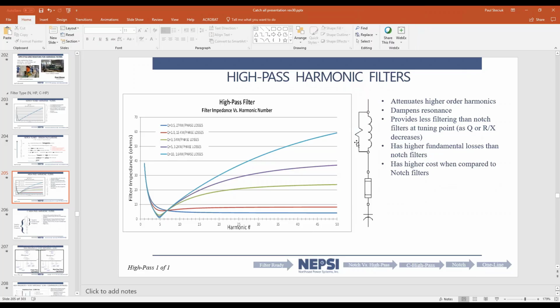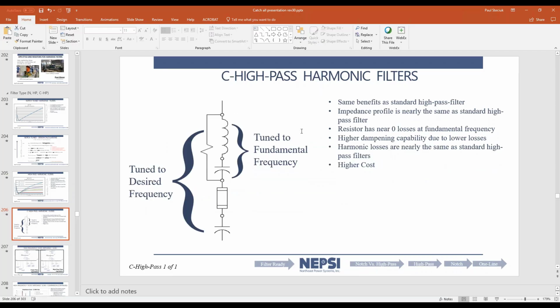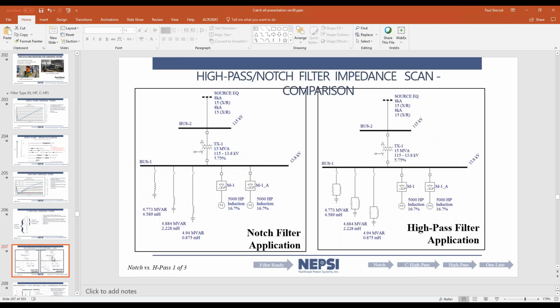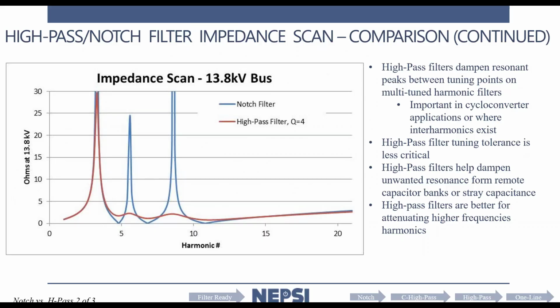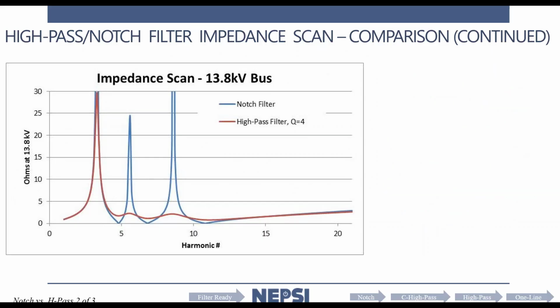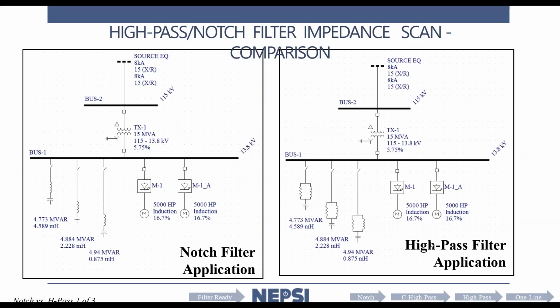So here you can see a high pass harmonic filter has a resistor in parallel with a reactor. There's also what's called a C high pass filter, which has a resistor, a reactor and a capacitor. So the interharmonics are cured with this C high pass and high pass harmonic filters. And I think I can best explain it on this next slide, that might show a comparison between notch filter application and a high pass filter application. So here I show an impedance scan for that situation where we have a notch filter application and high pass filter application.